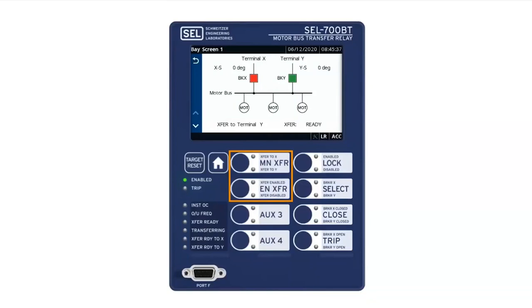The maximum breaker close time that the relay allows is 200 milliseconds. If you have a breaker close time that's longer than that, then doing a fast transfer or an in-phase transfer is very risky, because lots of things can happen at that time. Basically, the longer the breaker close time, the more sure you have to be that there is enough inertia in the system. But yes, those are the limits. If you have a high inertia, then you would allow for a long breaker close time. But ideally, you will want a fast closing breaker for this application.